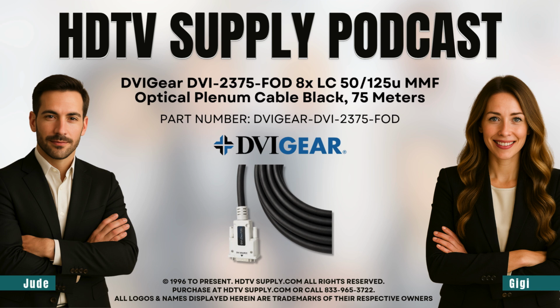If you run standard polyvinyl chloride, PVC cables through an air handling space, you're asking for a disaster. A fire would melt that plastic and instantly pump highly toxic corrosive smoke into every single room via the AC system. So to get that CMP rating, the jacket is engineered with advanced fluoropolymers, similar to Teflon. These specialized materials inherently resist combustion and self-extinguish. If they are exposed to direct flame, they emit minimal, less toxic smoke.